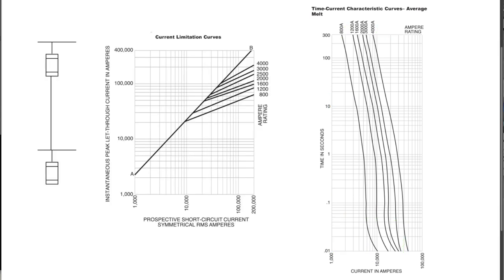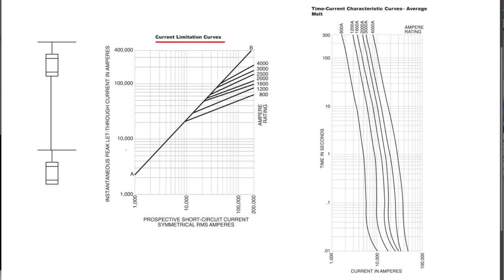Every fuse classification has its own chart. If the fuse is a current limiting fuse, it'll have a second chart that tells us how many amps will actually get through the fuse before it trips. A normal non-current limiting fuse will let all the fault current through until it trips, but a current limiting fuse will only let a subset through. The affected region is defined by these lines. On the left hand side is the instantaneous peak let-through current. We're not normally concerned with this, but what we usually are concerned with is the symmetrical RMS amps that get through.